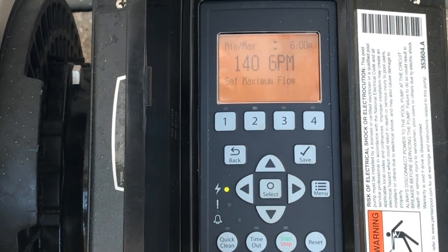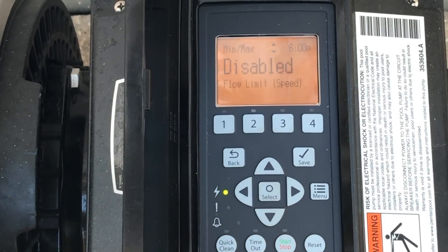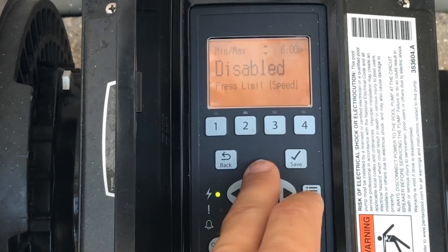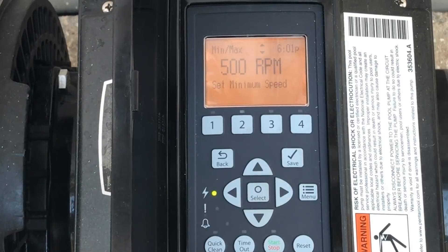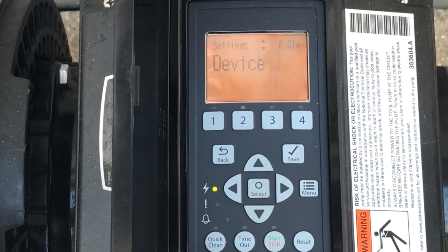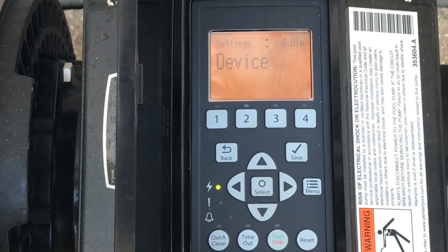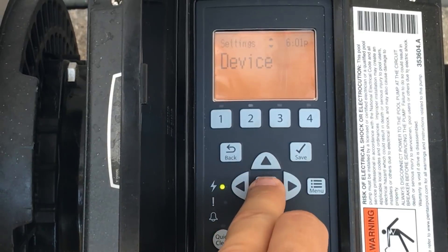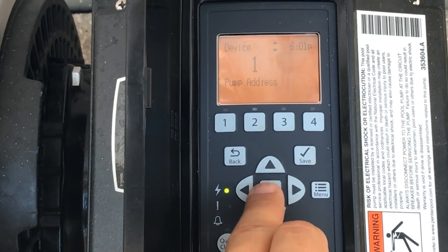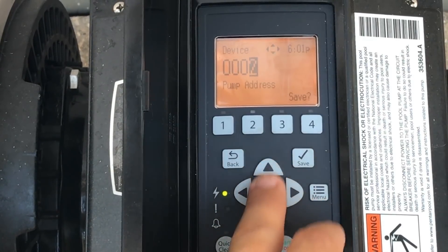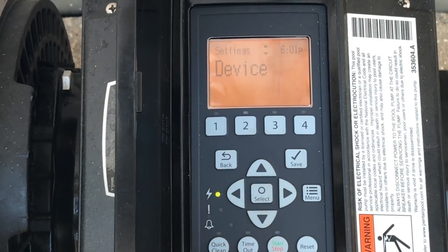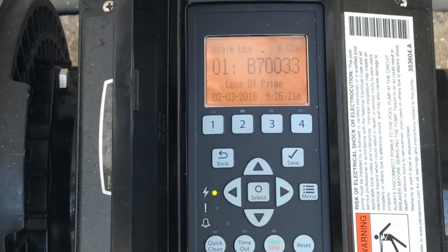If you have other systems like a heater, you want to make sure you're activating the flow switch. You also have the ability to change the maximum gallons per minute and the PSI. Under devices, if you have multiple pumps in automation — a spa pump and a main pool pump — you can change the address. This is the only pump, so we leave it at one and save.